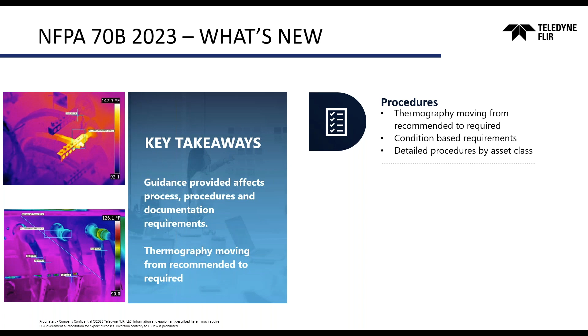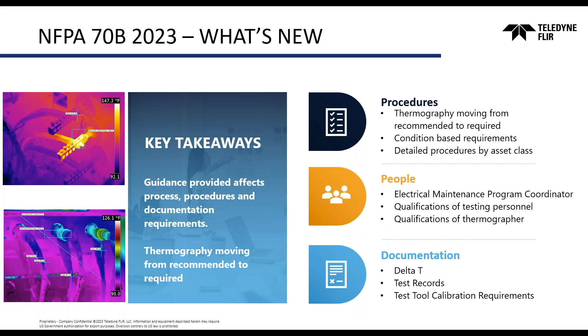On the people side, the document defines a role, the electrical maintenance program coordinator, and addresses some qualifications of both the testing personnel and the thermographer themselves. We'll dive a little deeper into that. And then the documentation piece. This is always an area where organizations struggle, regardless of electrical inspections or otherwise: maintaining good documentation. So we're going to call out within this presentation a little bit about delta T, or temperature differences, as well as the test records required for documentation, and test tool calibration requirements.